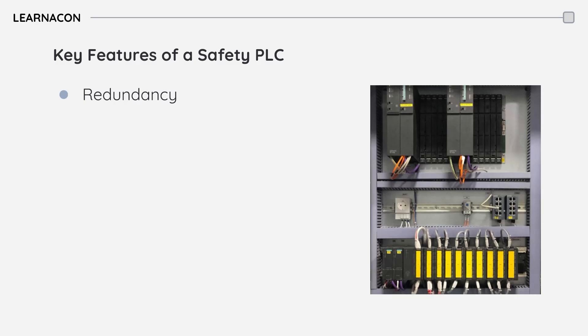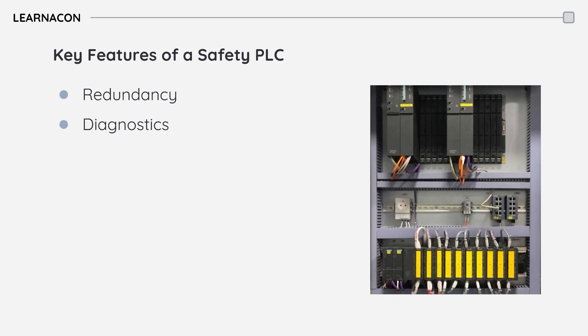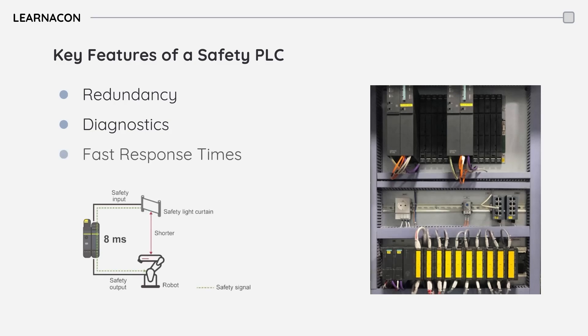They also have extensive self-diagnostics. The PLC continuously checks itself for any internal failures and if a problem is detected, it can trigger a safe shutdown. Finally, safety PLCs are engineered for extremely fast response times. In a safety critical situation every millisecond counts, and these PLCs are designed to react quickly and reliably to prevent accidents.